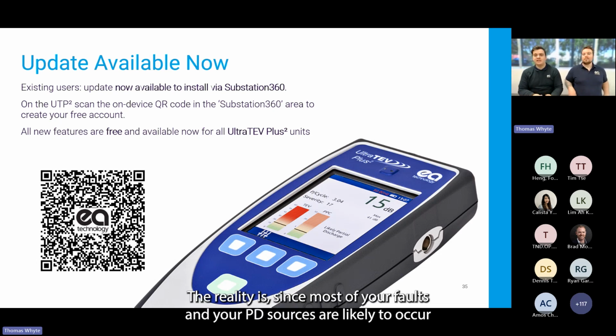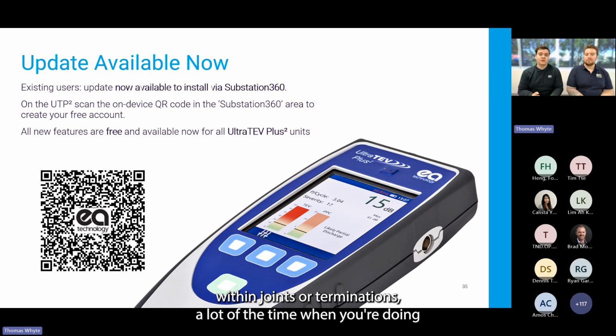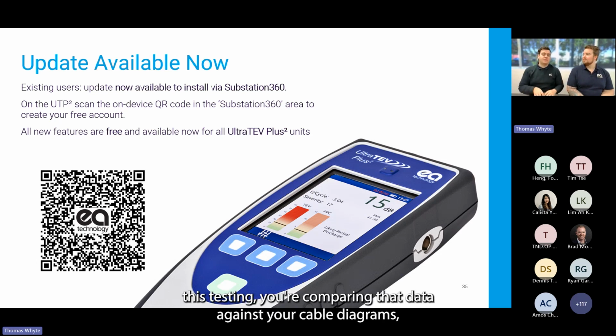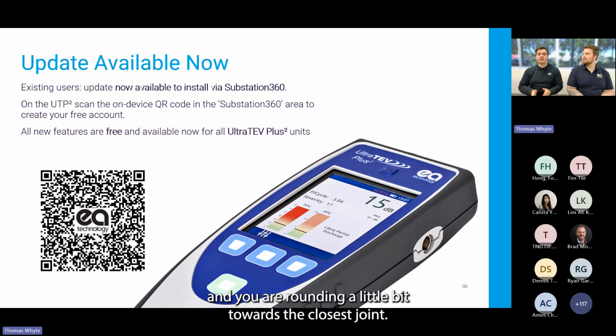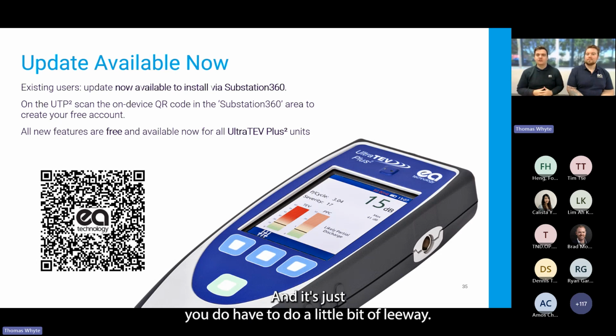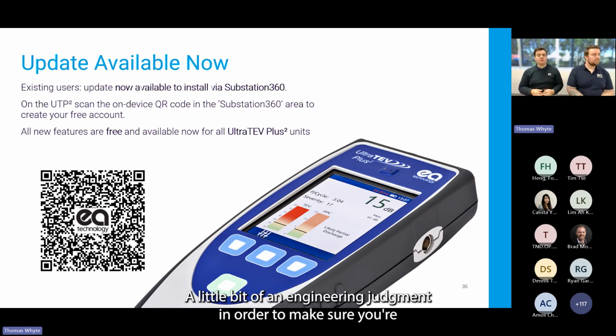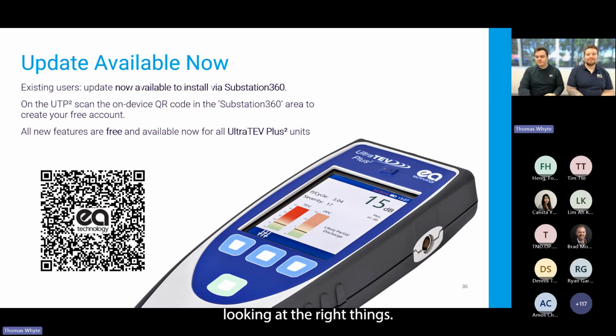The reality is, since most of your faults and PD sources are likely to occur within joints or terminations, a lot of the time when you're doing this testing, you're comparing that data against your cable diagrams and rounding a little bit towards the closest joint. You do have to allow a little leeway, a bit of engineering judgment, to make sure you're looking at the right things.